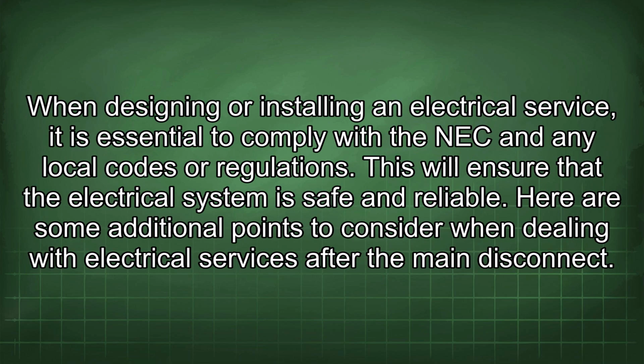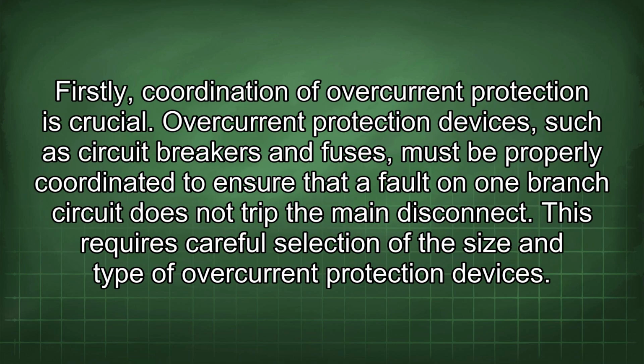When designing or installing an electrical service, it is essential to comply with the NEC and any local codes or regulations. This will ensure that the electrical system is safe and reliable. Here are some additional points to consider when dealing with electrical services after the main disconnect. Firstly, coordination of overcurrent protection is crucial. Overcurrent protection devices, such as circuit breakers and fuses, must be properly coordinated to ensure that a fault on one branch circuit does not trip the main disconnect. This requires careful selection of the size and type of overcurrent protection devices.